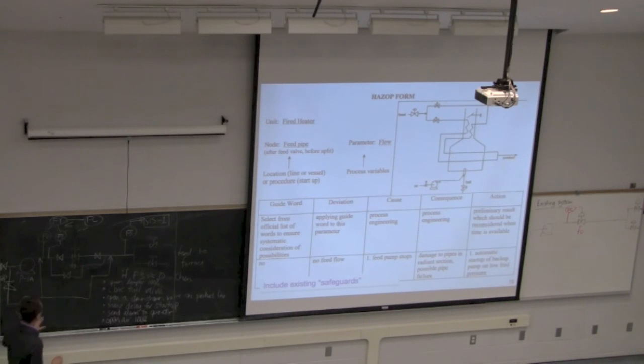So when you're in failure mode, it's something that's temporary and short term. I would argue that you should introduce your flow over there rather than here, because if you put it in over here, then this is going to become your normal mode of operation. People are just going to use this flow control system. Now that could also be good from a flexibility point. We're going to talk about flexibility next week. What if you use a lead-lag so you're not always running pump 1A, rotating? Okay, so that part of flexibility we're going to talk about next week. So you can argue from a flexibility point of view you want it over here. From a pure safety point of view, where pump 1B is only for backup use, you introduce it here.